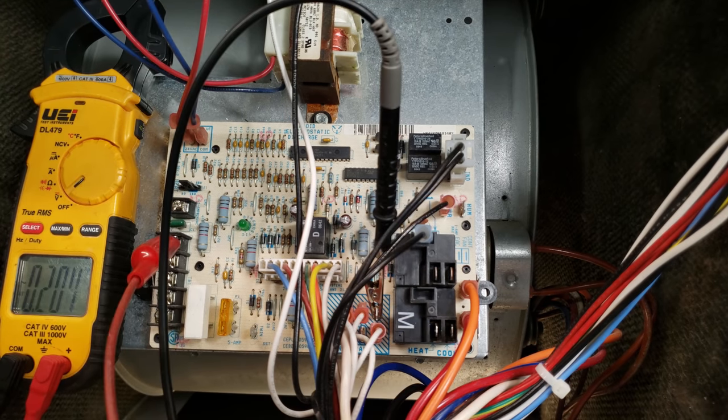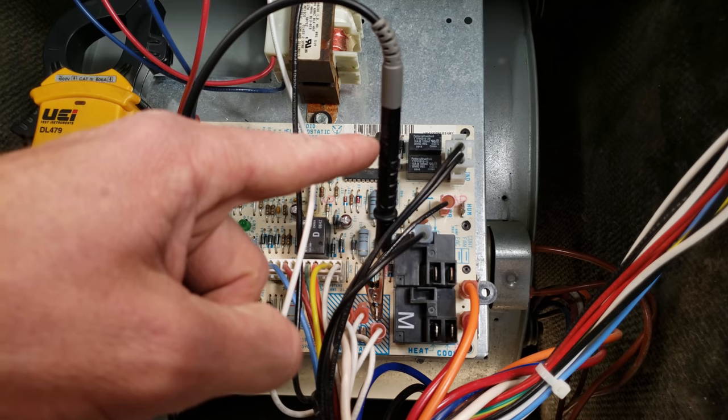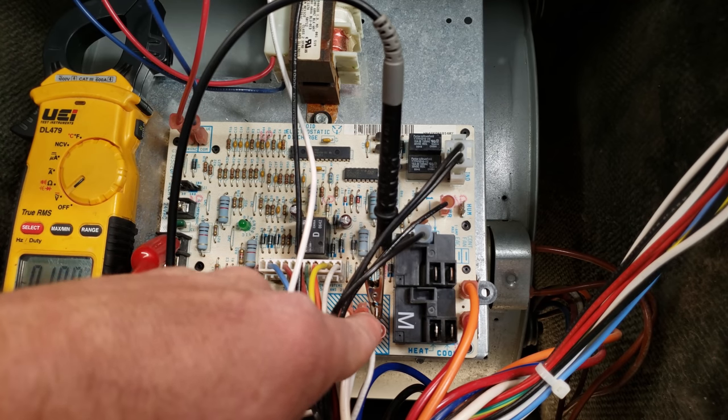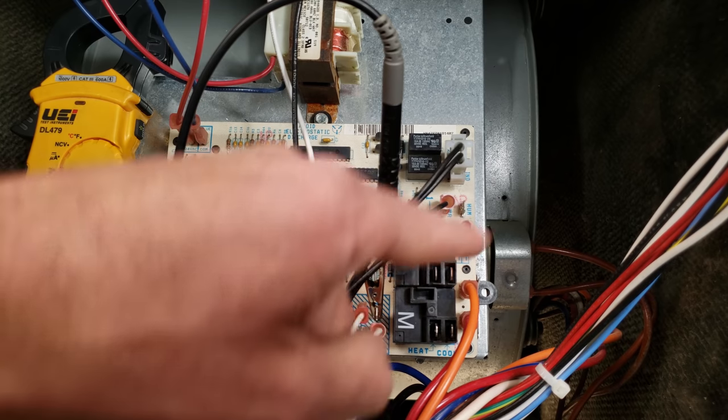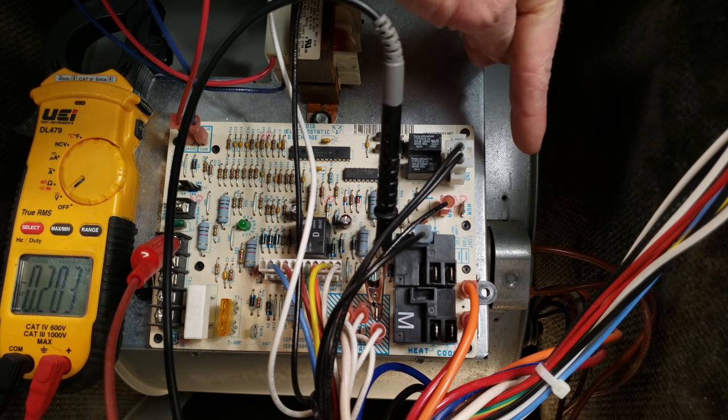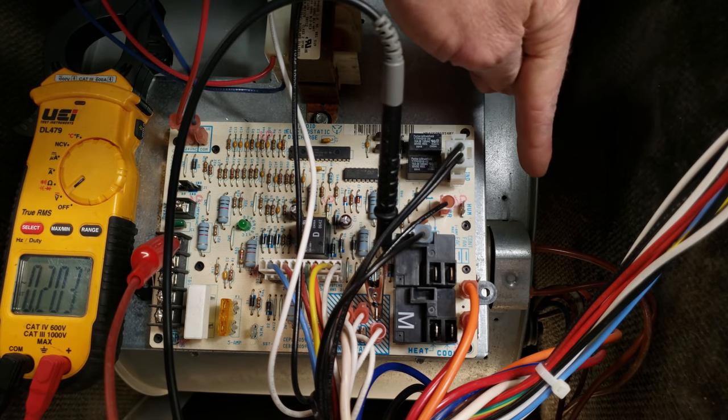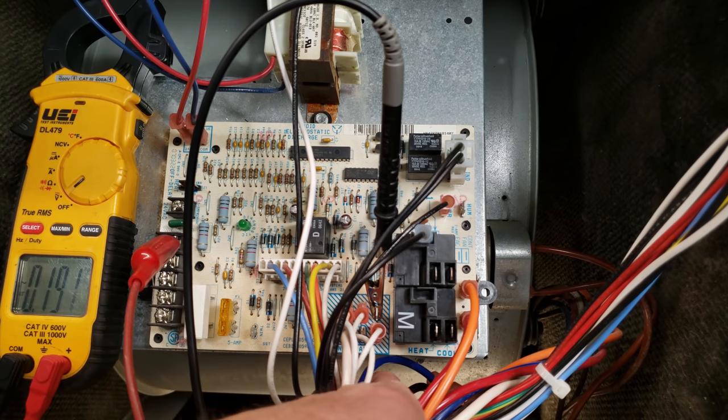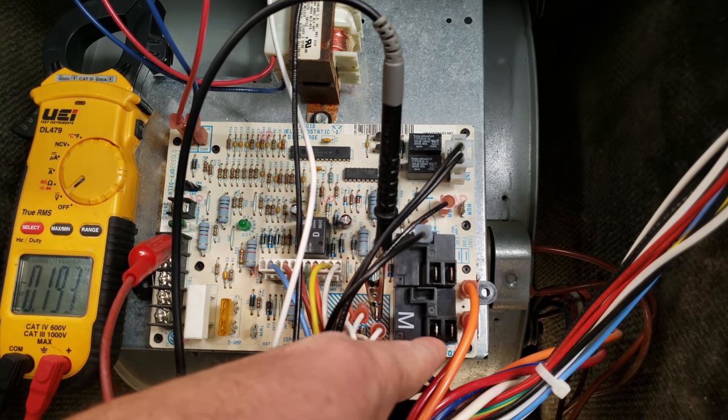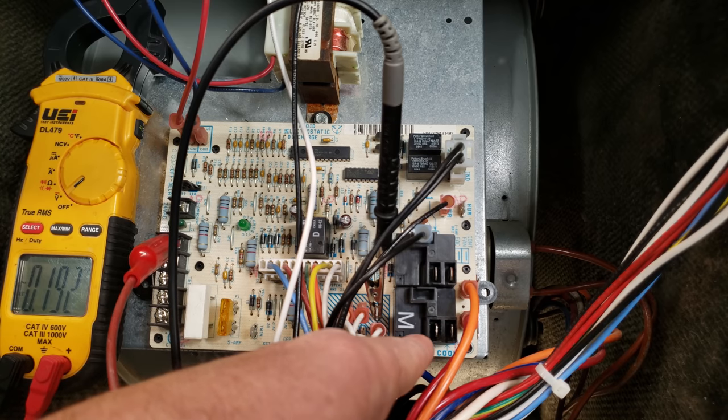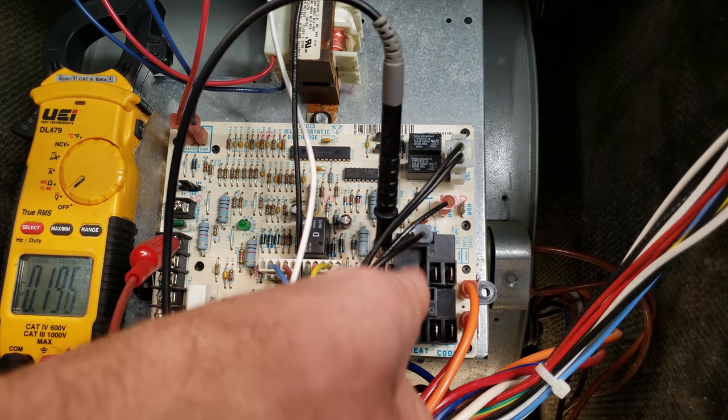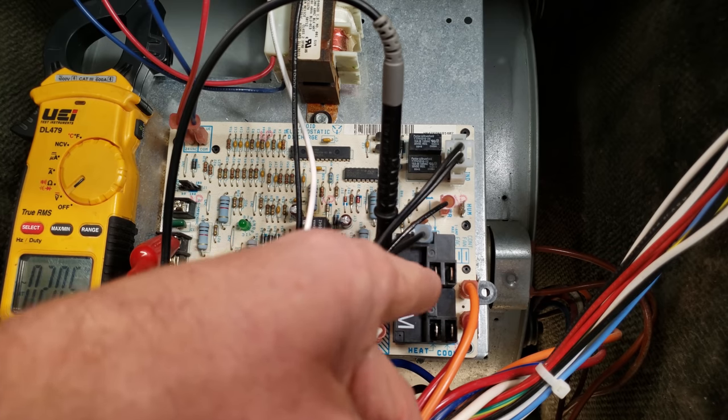Now we have the multimeter set on voltage, and we have one probe mounted to the common neutral bar, and that's connected to the common wire to the blower motor. This is a 120 volt permanent split capacitor blower motor, and I disconnected the wires that are on the heat and cooling terminal of this relay because I want to check for voltage on the relays to explain how this is working.